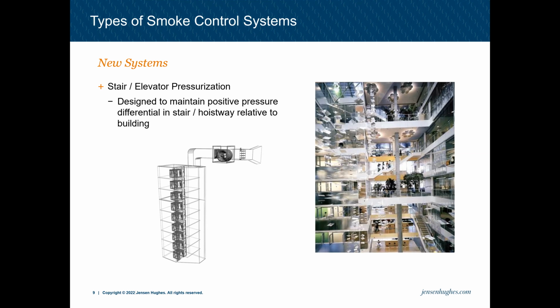The main idea for this is that during a fire event, fire and smoke is usually pretty lazy, so it'll move to the area of the path of least resistance. Shafts, a stair shaft and an elevator shaft, basically act as a giant chimney. So if we have a fire on the second floor, that smoke would normally travel to the path of least resistance. So this stair shaft is going to act as our chimney.